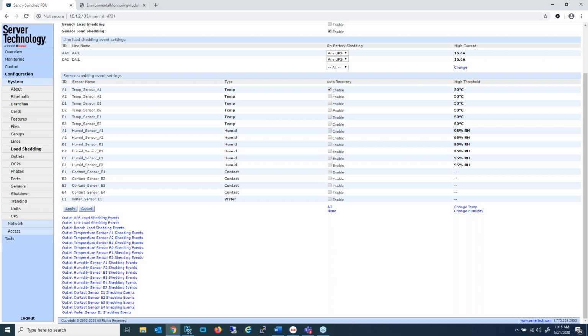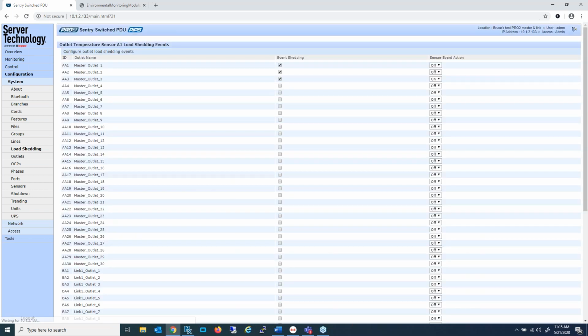So we're not going to go through all of them, but I am going to take a look at a temperature sensor event for the first sensor on the master unit. So this is where you configure which outlets will be switched off or on. I've selected outlets 1, 2, and 3, and over to the right we have a choice for each. That is, when an event occurs, you can actually choose to have an outlet switch off, or if an outlet is off, you can have it switch on.